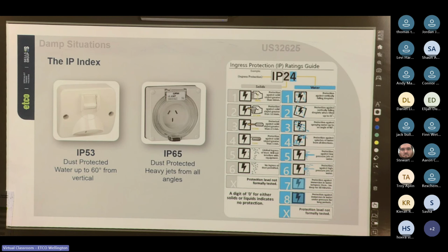Cool. So dust protected, heavy jets from all angles. One thing you can do if you don't want people to turn off your hot water is you can use a lockable isolator and you can lock it in the on position. Most PDL 56 series isolators, you can lock them in the on position. So the reason you might do this is for things like your outdoor hot water units or for your heat pumps. You can lock it in the on position so people can't screw with your power or screw with your heating or your hot water.